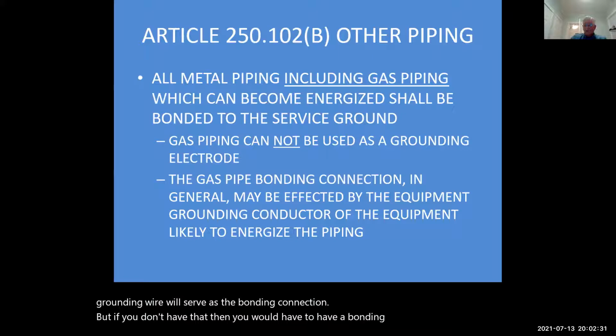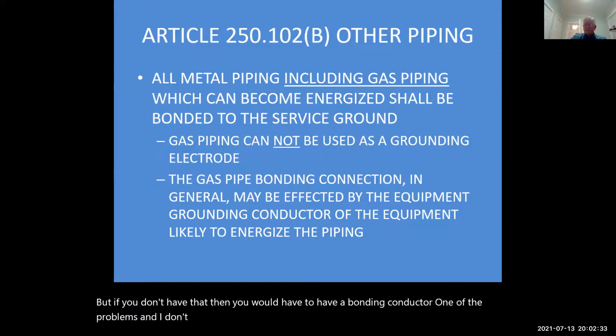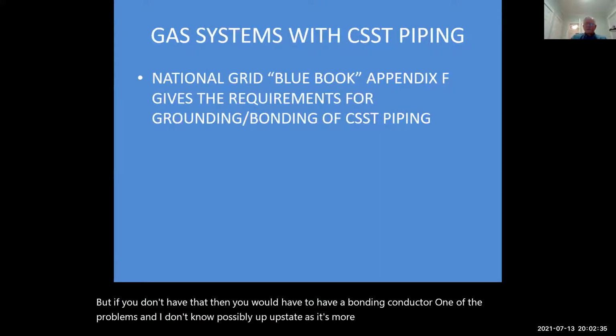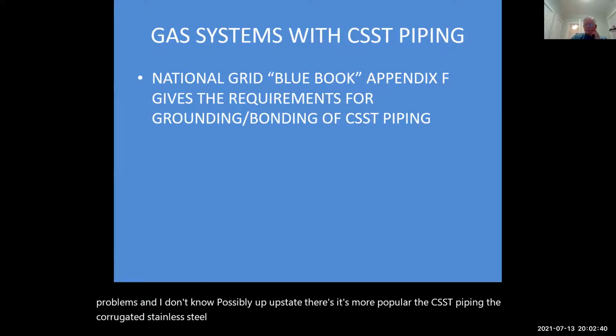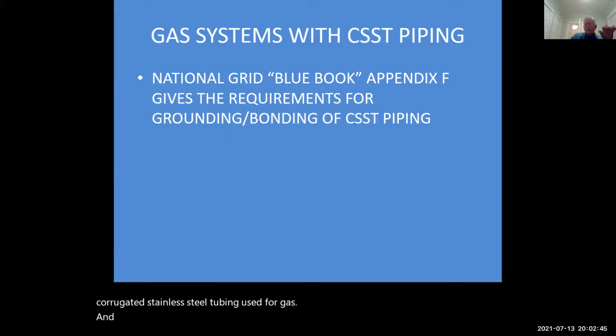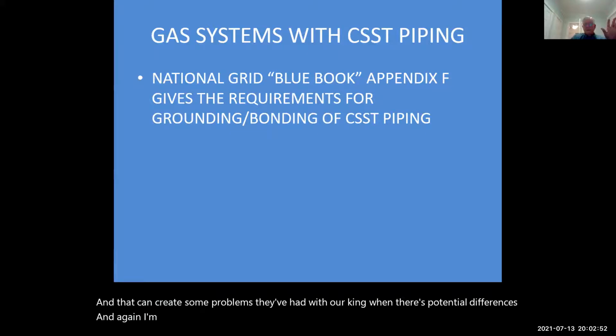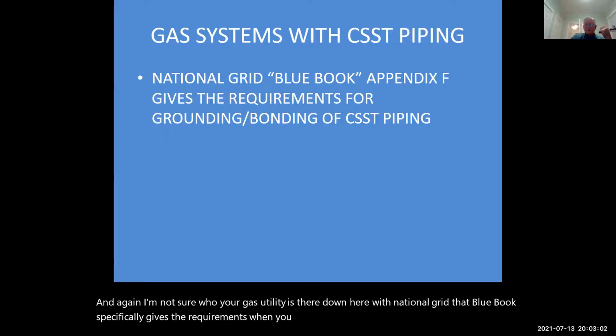One of the problems, and I don't know, possibly upstate it's more popular, is the CSST piping, the corrugated stainless steel tubing used for gas. That can create some problems. They've had arcing when there are potential differences. And again, I'm not sure who your gas utility is there. Down here with National Grid, their blue book specifically gives the requirements when you have CSST in use, and what the grounding and bonding requirements are.